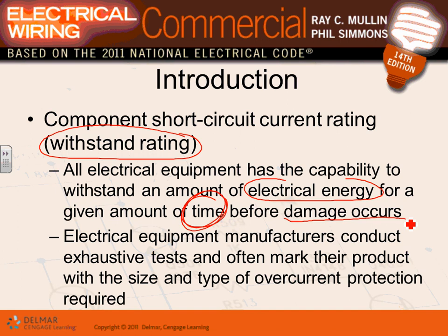The electrical equipment has the capability to withstand a certain short circuit current, and how long the equipment can handle it will decide the withstand rating of this equipment. Typically they give you a withstand rating for 5 seconds. After 5 seconds, your equipment can explode, depending upon the damage curve, of course.